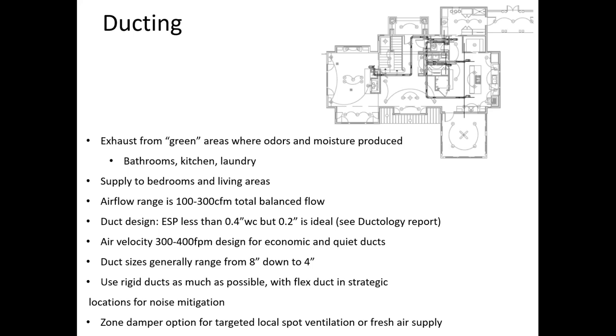The airflow range is 100 to 300 CFM balance flow. So you'd set this in relation to both the house size and the number of spaces to ventilate. For duct design, hopefully a static pressure goal of about 0.2 inches of water would be ideal. We've written a report on doing these sizing calculations and why, and what a good duct network and design looks like. Keeping air velocity at 300 to 400 feet per minute results in good, quiet ducts and low fan power. But overall the sizing will range from 8 inches down to 4 inches.